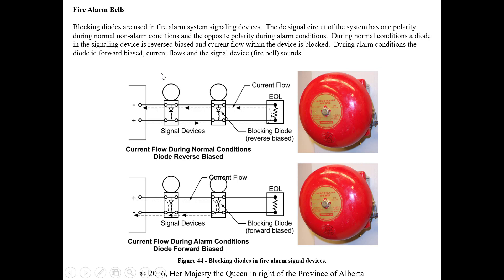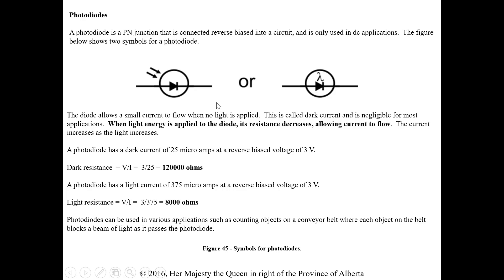Another application is fire alarm bells using a signaling circuit. A DC signal circuit has one polarity during non-alarm conditions — current flows through the end-of-line resistor, which the fire alarm panel reads. When a sensing device such as a smoke or heat detector triggers an alarm, the panel reverses the polarity to the bells. The diodes that were reverse biased are now forward biased and start ringing the bells. During normal conditions they're reversed; during alarm conditions they're forward biased and the signal device sounds.